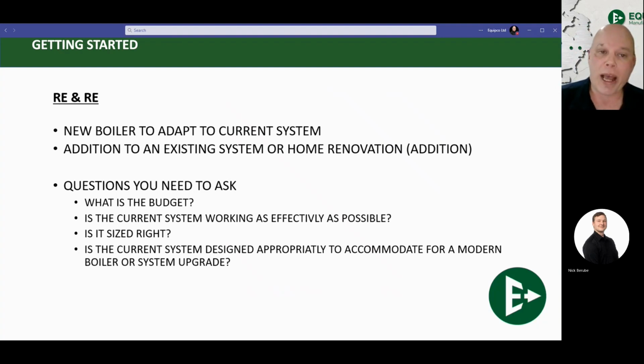The second question you want to ask for a re-and-re is: is the current system working as effectively as possible? Meaning essentially, did the boiler ever work right in the first place? Did they have hot and cold spots in amongst the house? Was the heat effective? Was the cooling effective? Did it work as the homeowner intended it to and as they wanted it to? If it didn't, this is a good chance to dial in the finer details of a hydronic system, make sure we get it working right moving forward.